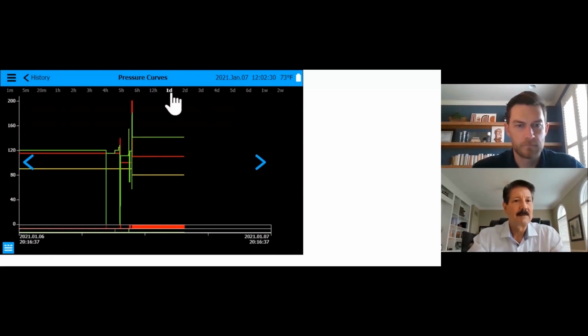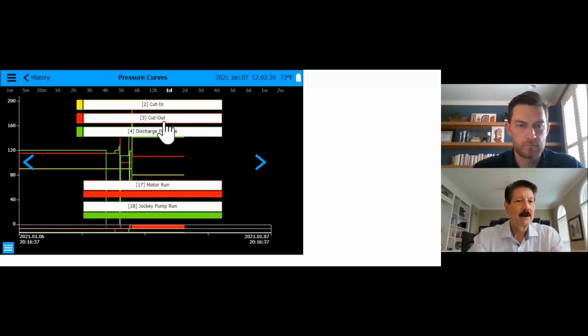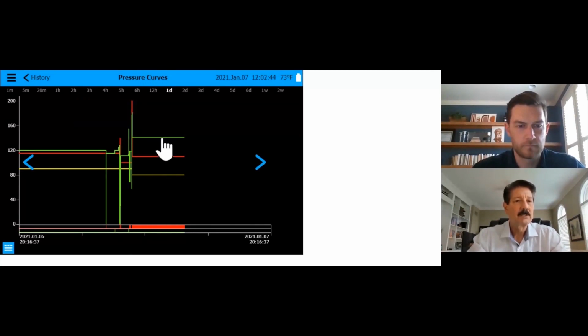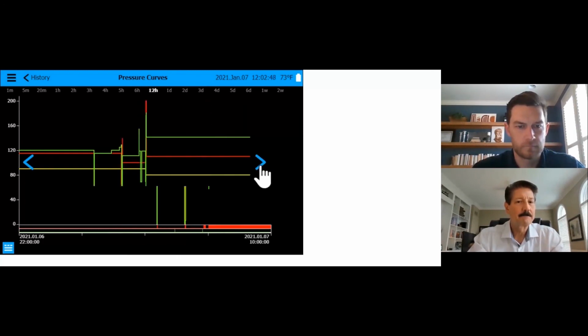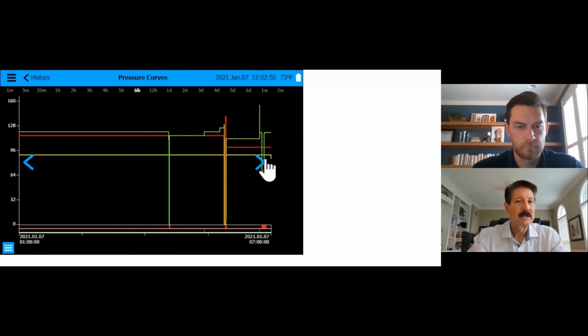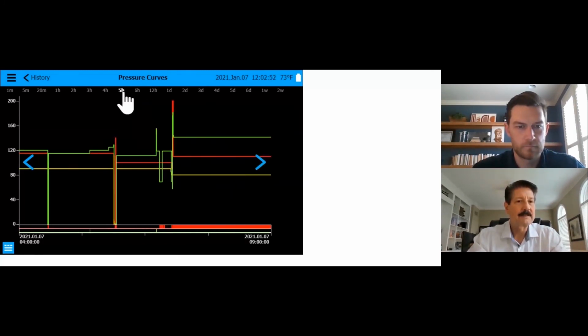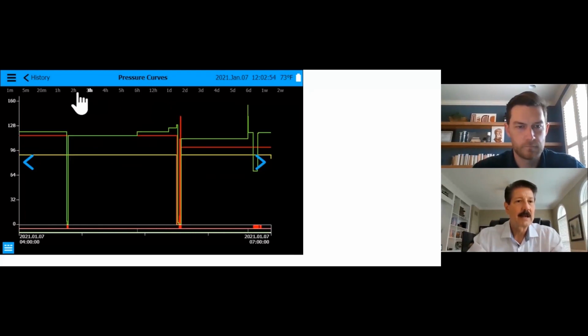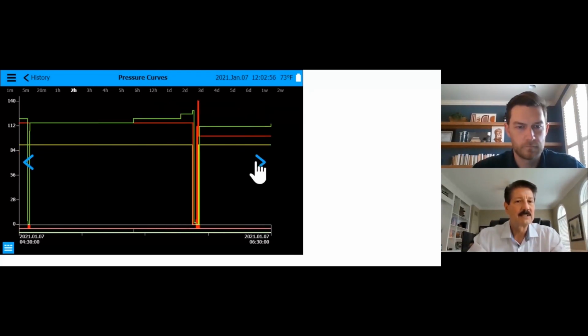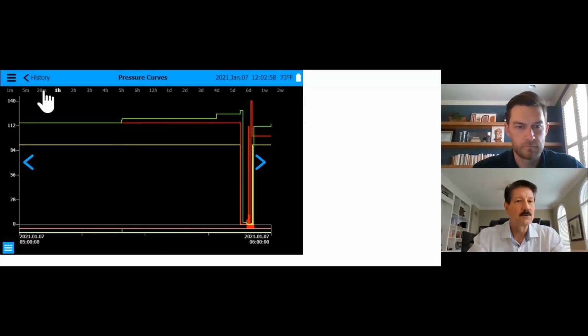As you can see, I'm looking at 1 day here. So look at what we have here: cut in, cut out. Discharge is green. Jockey is green on the bottom, and the motor running on the horizontal plane is red. So in this particular case, that's a day. I'm going to spread these out to 12 hours. And the reason I'm doing that is because we're drilling down: 5 hours, 3 hours, 2 hours. It spreads it out much easier to see. 1 hour, 20 minutes.